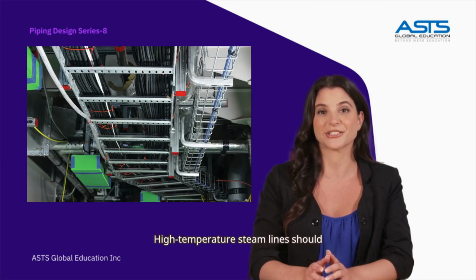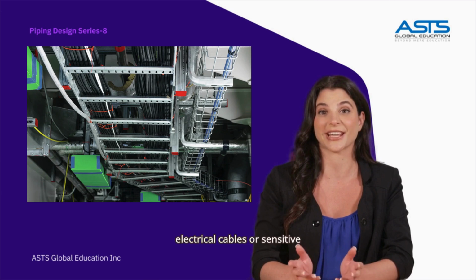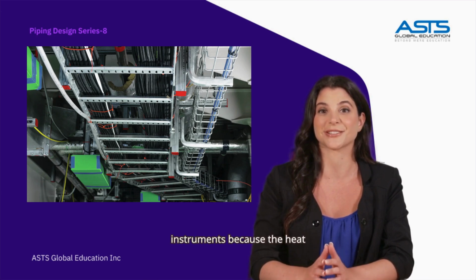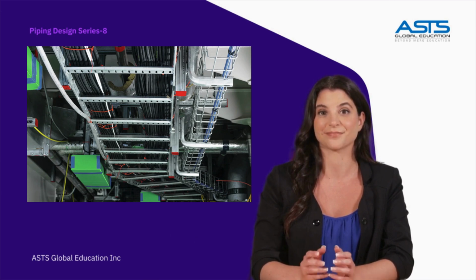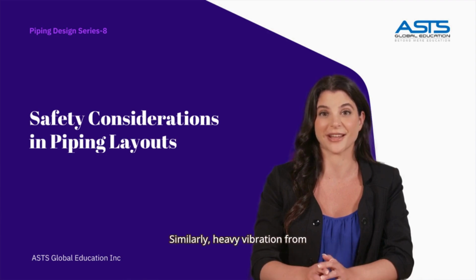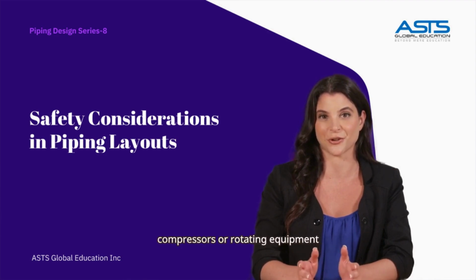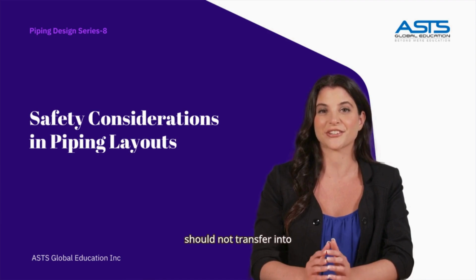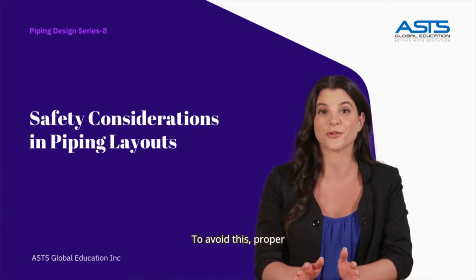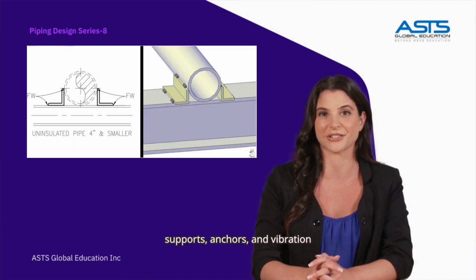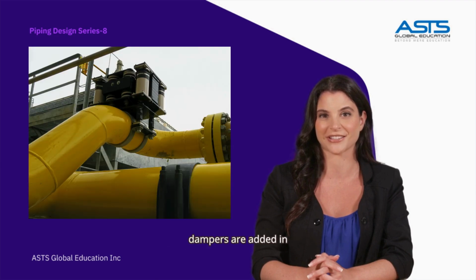We also have to think about thermal and mechanical safety. High-temperature steam lines should not be routed near electrical cables or sensitive instruments because the heat can damage them. Similarly, heavy vibration from compressors or rotating equipment should not transfer into connected piping. To avoid this, proper supports, anchors, and vibration dampers are added in the layout.